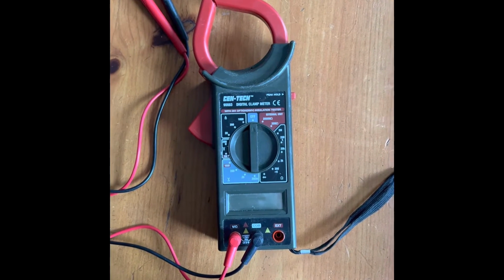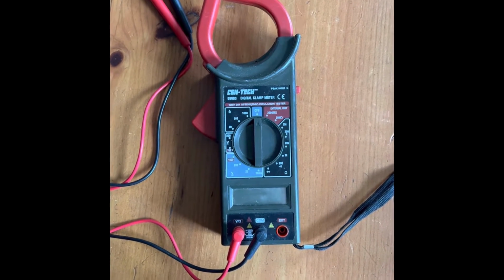Today I'm going to talk about the capabilities of using a digital multimeter, the safety precautions when using the meter, the display of the meter when a measurement is out of range, and I'm going to verify that an outlet is live, determine if a battery is charged, and perform a continuity test on a basic two-way light switch. Today I'm using a Cen-Tech digital clamp multimeter to perform my tests.